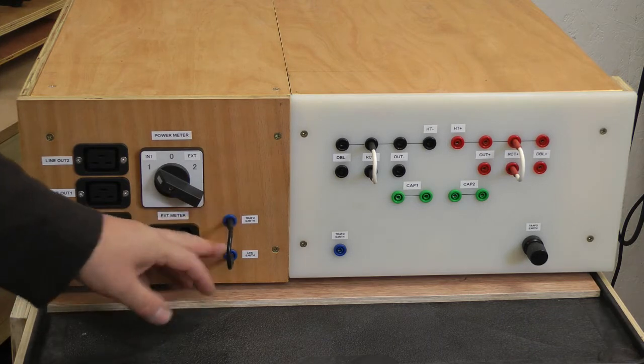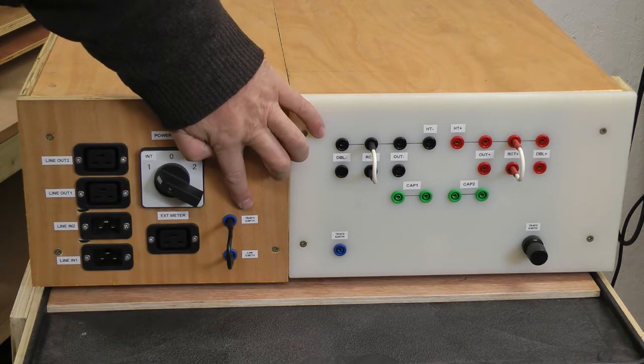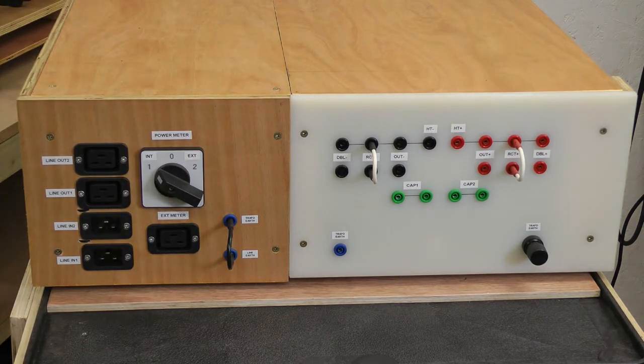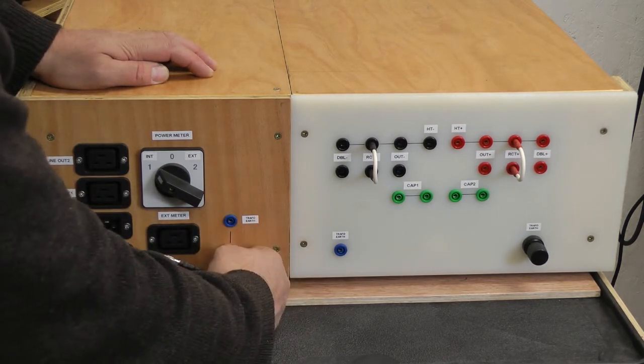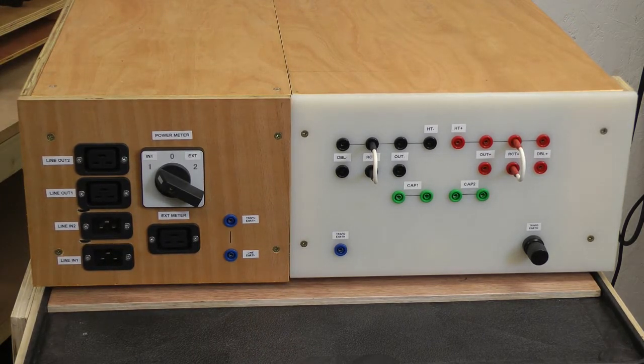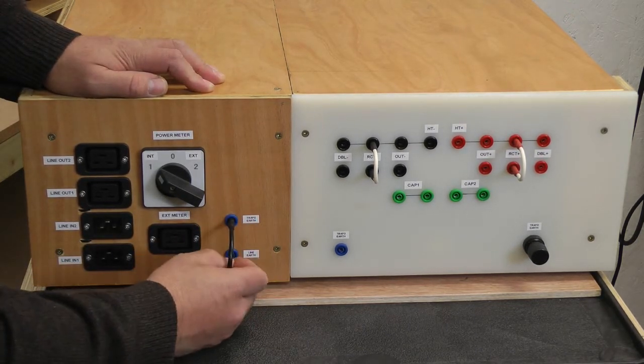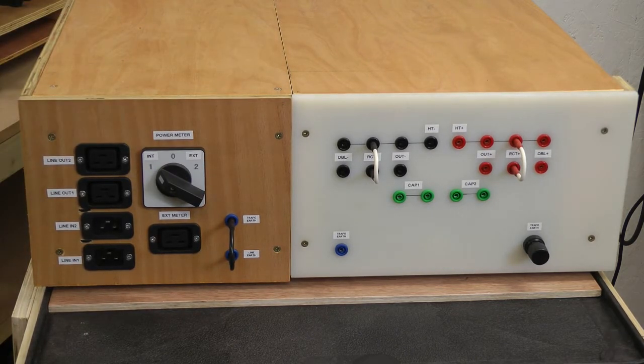Then we have our primary earth connection. So this end is line earth. This is the transformer earth, or basically what, if you select the jumper options, what can actually be connected to the core of the transformers. If we remove that, we essentially float the transformers. So we're not connecting the transformer to line earth. That could be particularly important, for example, if we are running, depends where the reference is, we're running 3 transformers in series, and we've got the bottom transformer pushing negative, while the other two transformers in series above it are pushing positive. Then, for example, we would want to disconnect the transformer earth from the line earth. Okay, I'll come back to the output panel once we've gone through the various other stages.